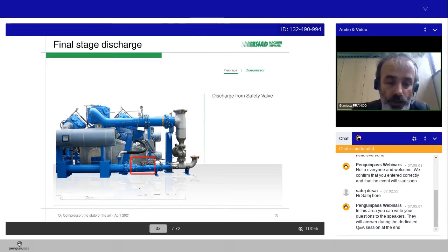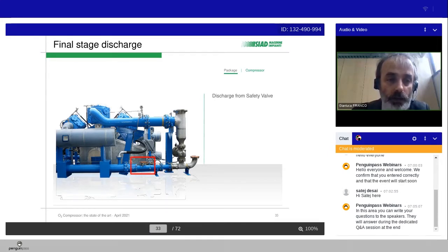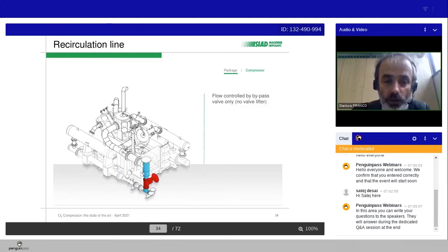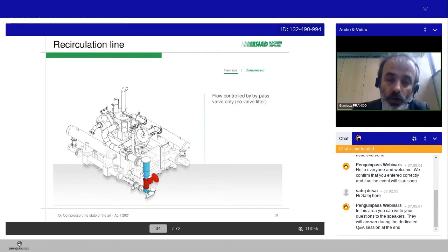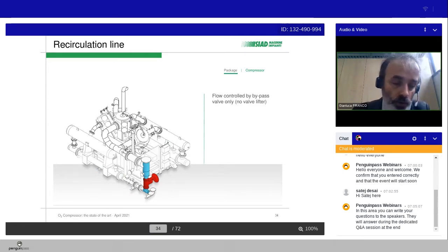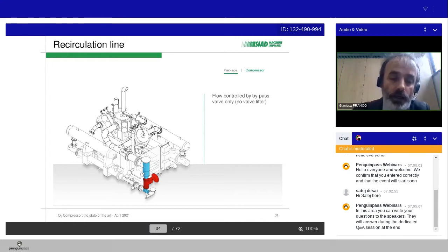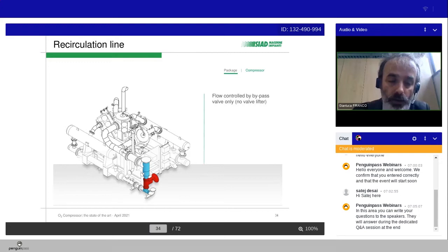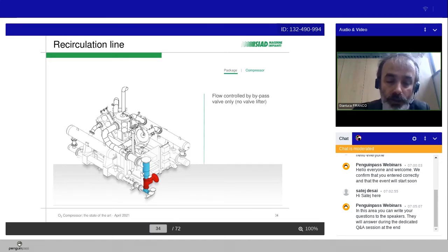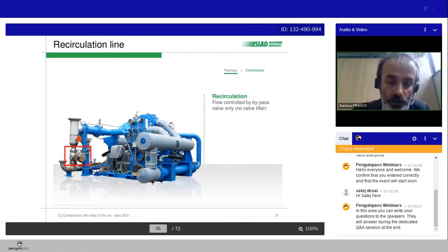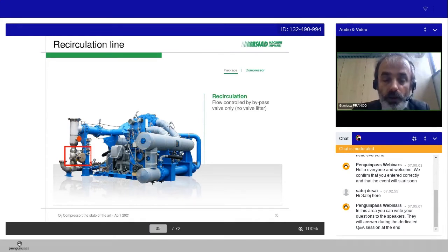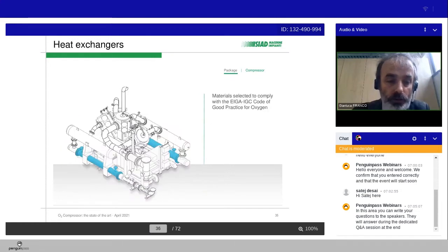Here you can see the picture of the real machine in the final stage discharge. And as I anticipated a few minutes ago, the flow is controlled by the bypass valve. We cannot use the valve lifter. And typically the flow is controlled by a recycle valve with zero to 100% total flow regulation, with also the energy saving effect. So the recirculation is obtained by the bypass valve only without valve lifter.